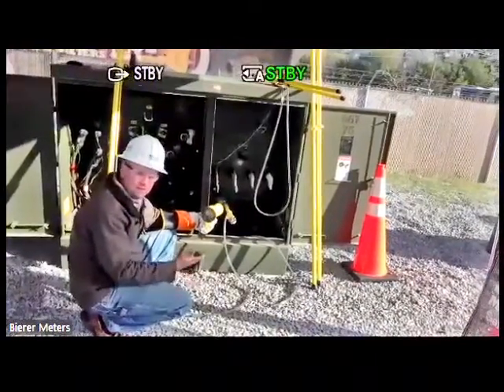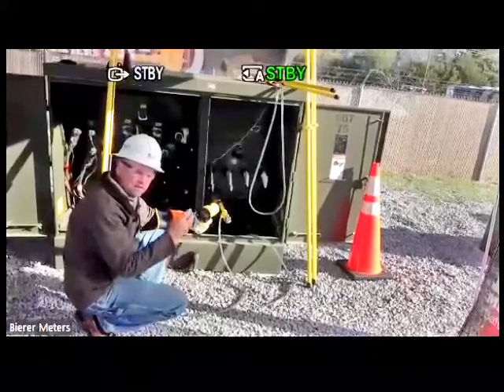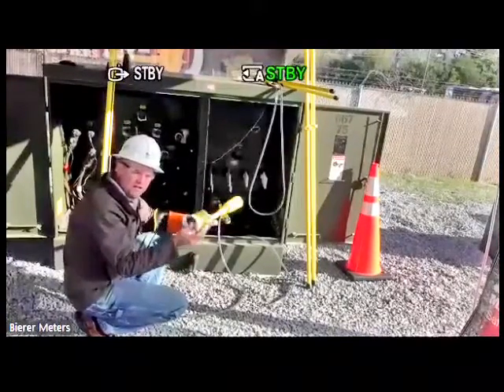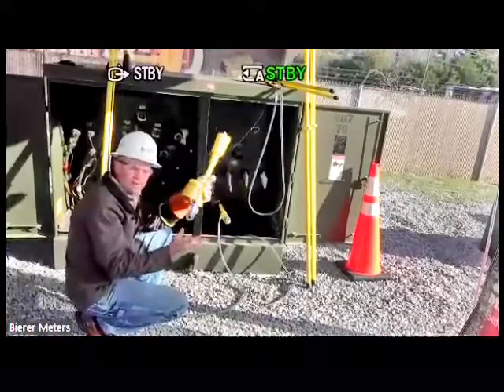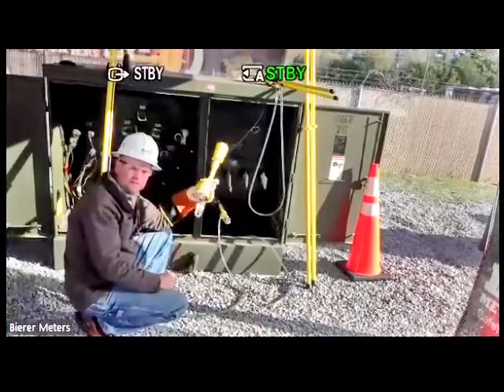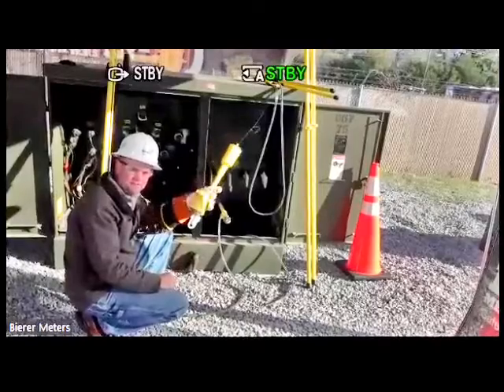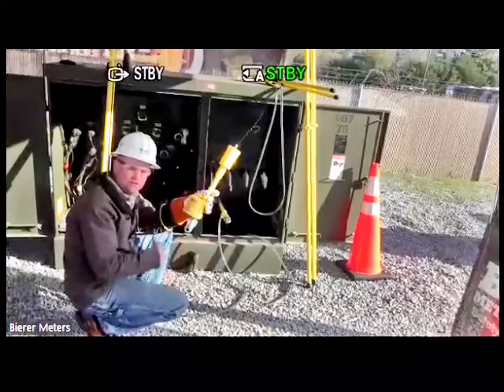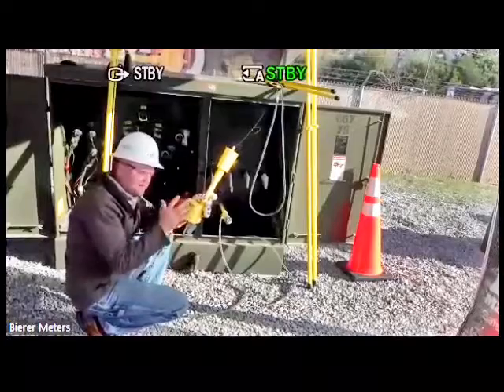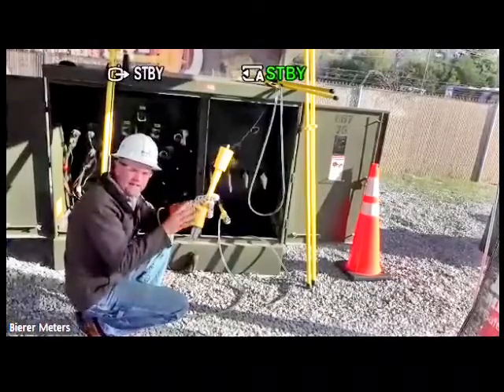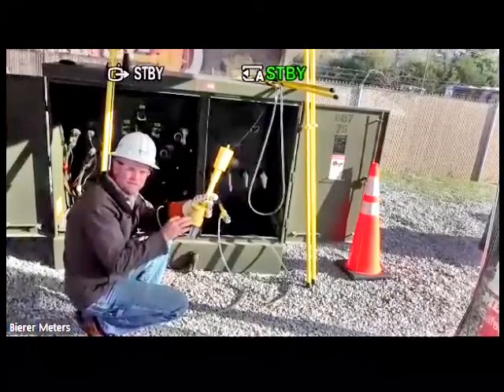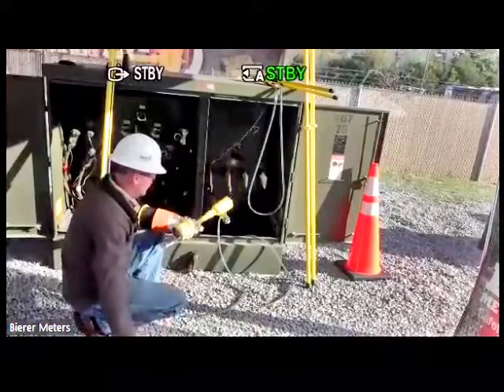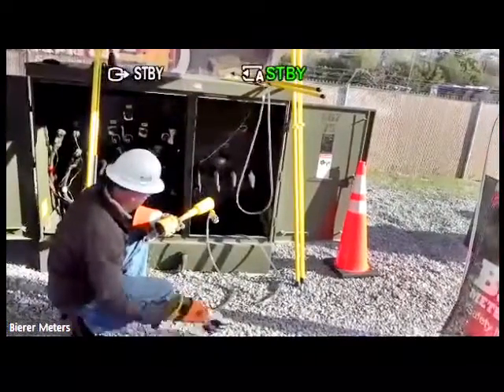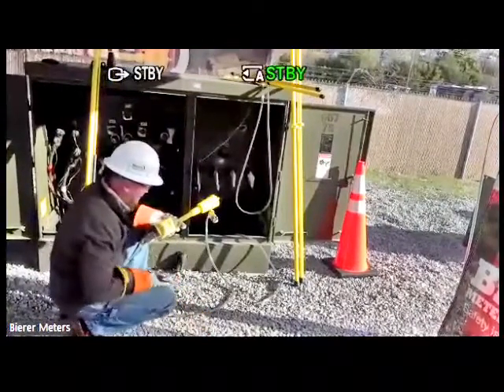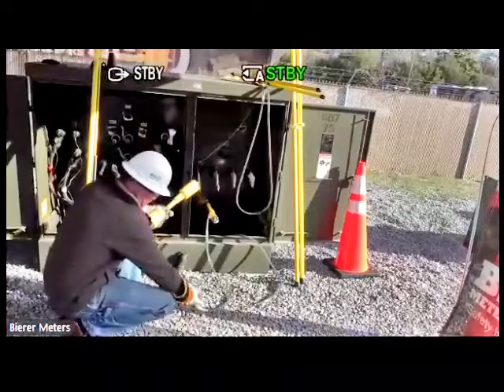Some utilities will order our flat clamps and attach it to a steel structure. They'll have a 50-foot cable and they'll go up in a bucket and they'll check for induced potentials and see exactly how much induced potential they have on those conductors before they put grounds on it. Again, extremely accurate. It's going to tell that line exactly how much potential is on there. So within 1%. So what I'm going to do is go ahead and use this scenario with my second probe. And again, I'm going to look for that potential.